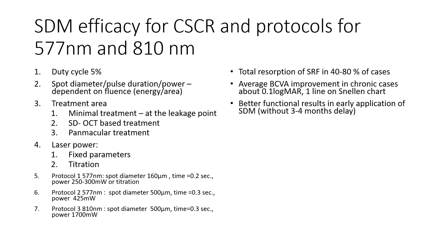Subthreshold diode micropulse is a truly non-damaging retinal therapy that can be used with different laser wavelengths. What's common is the duty cycle, which has been empirically set at 5% as the safe value. We use different spot diameter, pulse duration, or laser power, which can be calculated from the laser fluence. There are different approaches to treatment area, starting from minimal treatment that targets just the leakage point, through SD-OCT-based treatment, to panmacular treatment that mobilizes a large number of RPE cells in the posterior pole. Laser power can be applied in two different ways: by fixed parameters or titration. However, the second form of application bears the risk of overtreatment. I give you a few examples of laser protocols at the bottom of the slide.